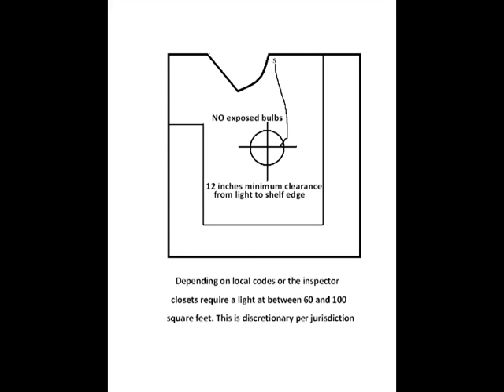Now generally, there's no specific code on square footage that I know of that determines when you need a light, but most of the inspectors I talk with want a light installed when a closet approaches between 60 and 100 square feet. 60 really is a good number, but one thing to remember is no exposed bulbs.